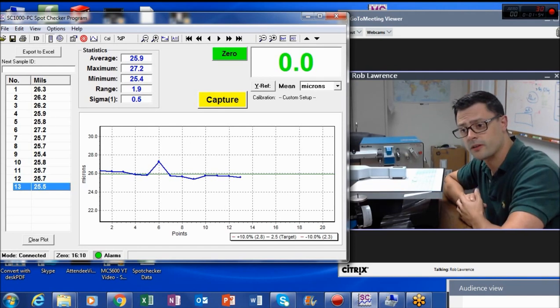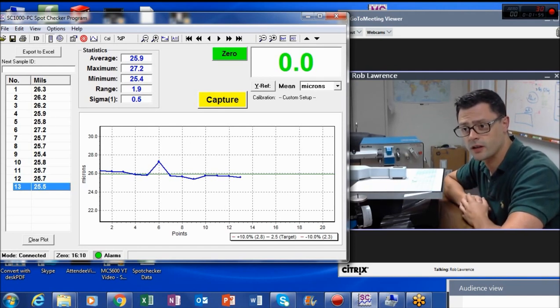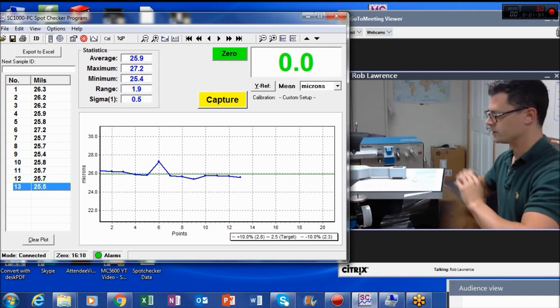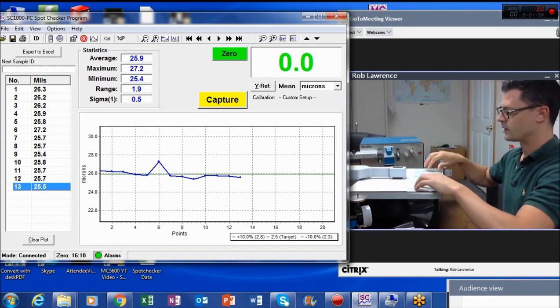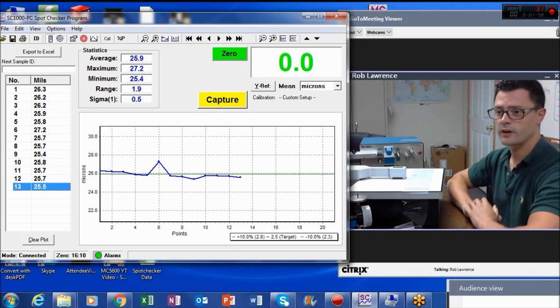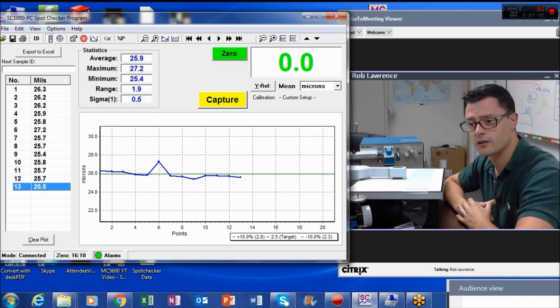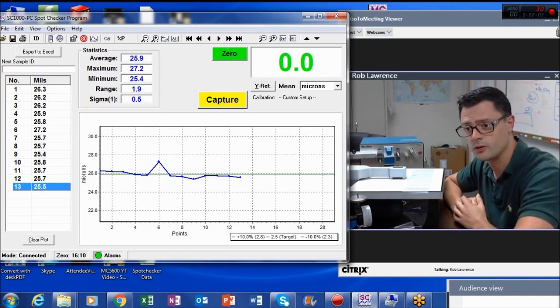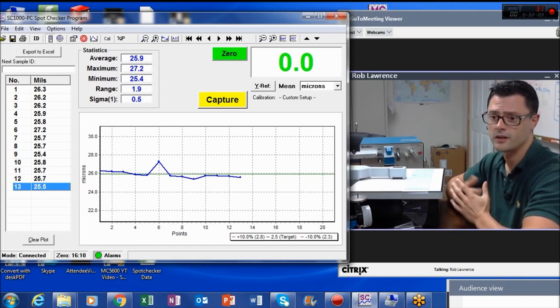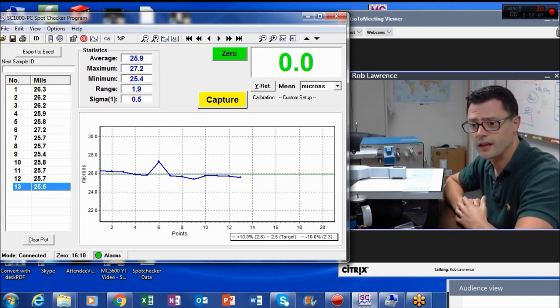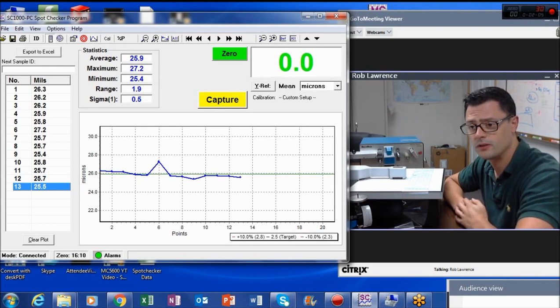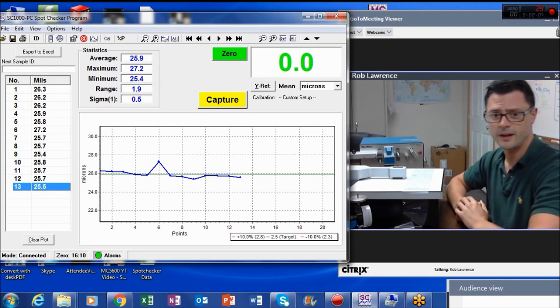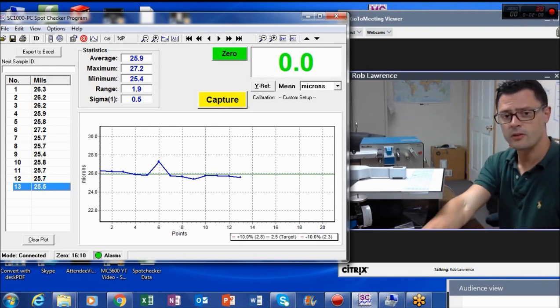You can calibrate the gauge using a NIST traceable method, which is done by the user, actually. So it's very easy to use, and there's no yearly calibration fees from Solvetech or anything like that.